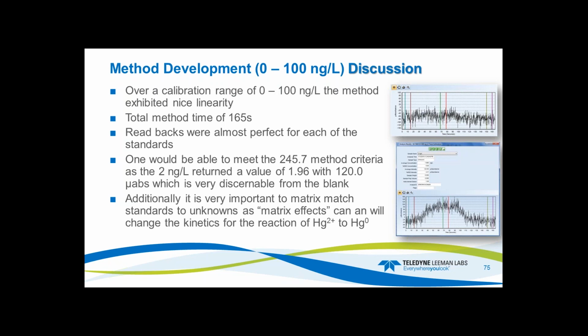Total method time is 165, but you're working with ultra-trace, so here you're going to charge more for those values, so it's acceptable to have a longer sample time. The readbacks are almost perfect. Now, this method is acceptable to 245.7. I just showed you a calibration point of 1.96 response for a 2 nanogram per liter with 120 microabsorbance units, very discernible above the blank. As long as you meet the quality control, you can use it for 245.7. And same thing for the matrix match.